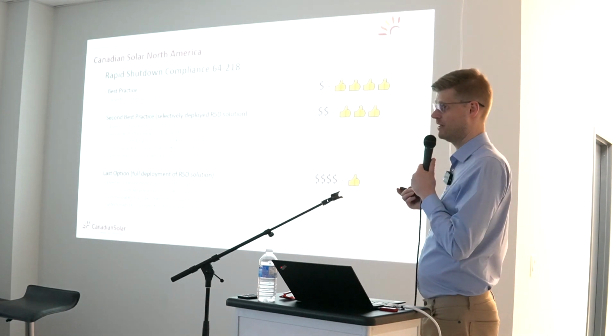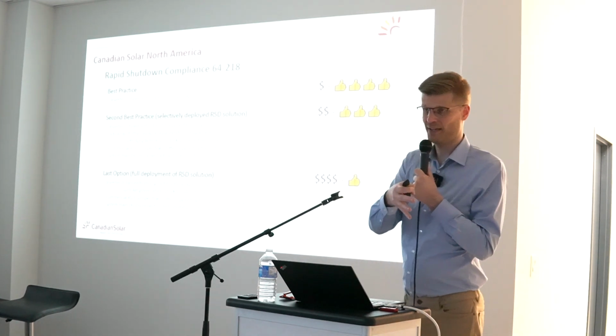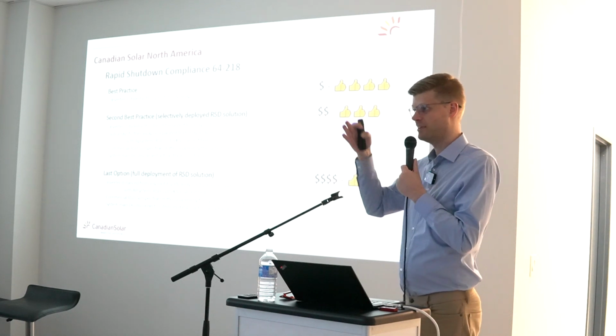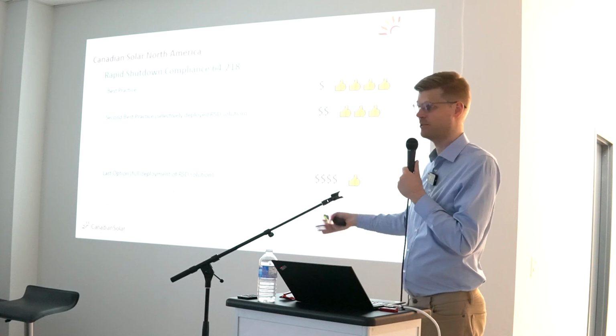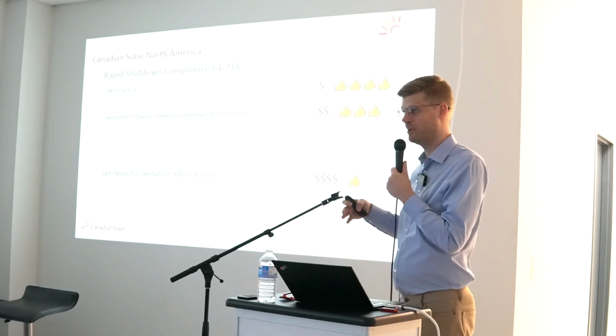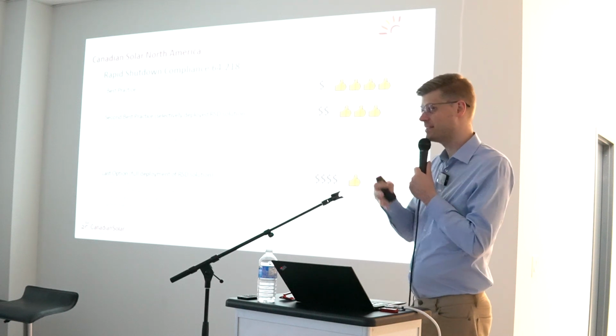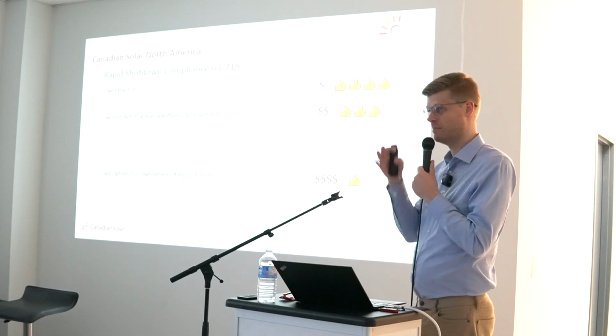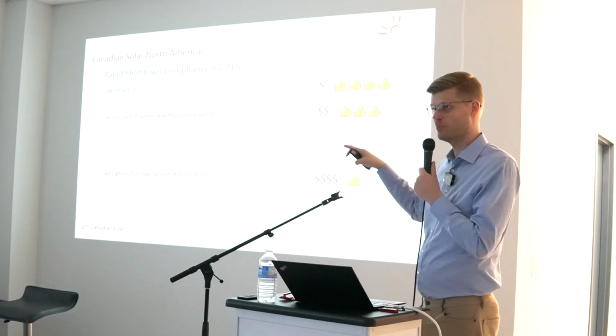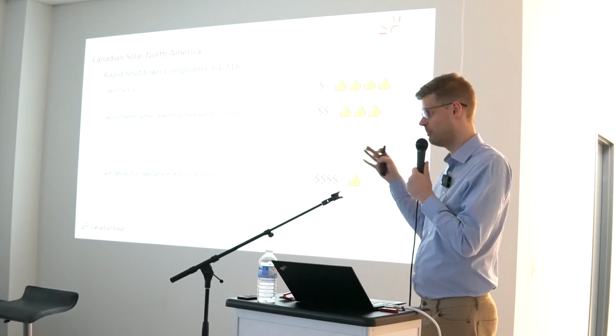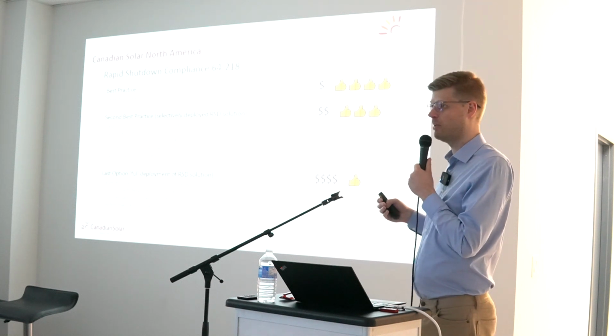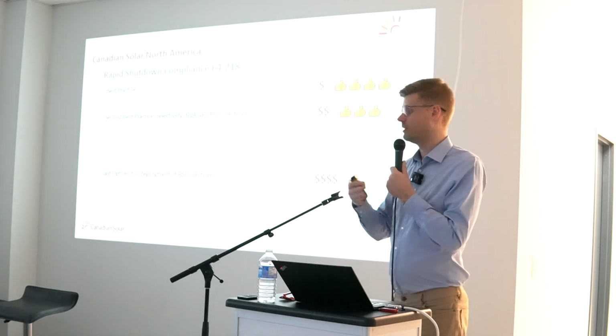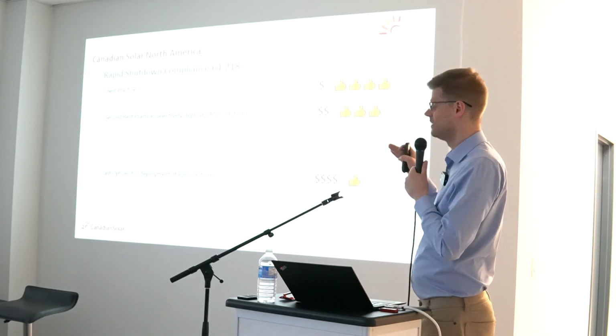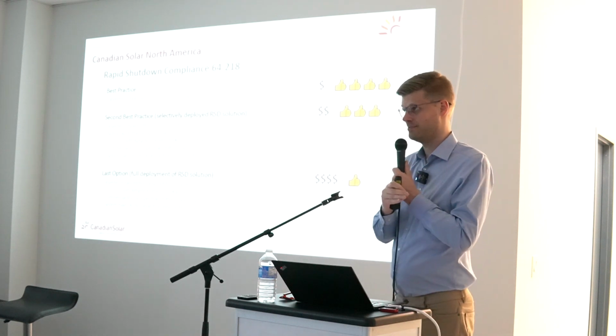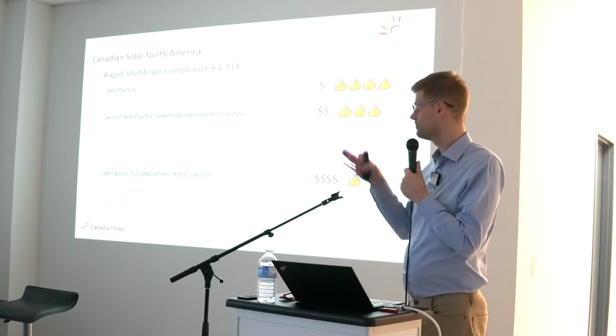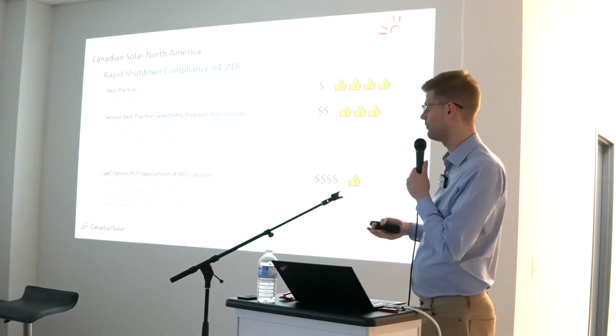If you cannot do that, because for example, your commercial rooftop system has a big array and you have smaller sub-arrays based on the layout of your roof, that there may be some HVAC units or maybe a different type of building that was added to a building that you have to bridge, then you might have a big system, let's say 60% or 70% of the system is in one big array, and just a few strings are on smaller roof segments that are further away than 1 meter each, so 2 meter total. At that point, you can only be compliant with the small one or the big one. So the best compromise here is that you install the inverter close to the largest system of your roof, the largest array, because that system is then, similar to number one, automatically code compliant for rapid shutdown.